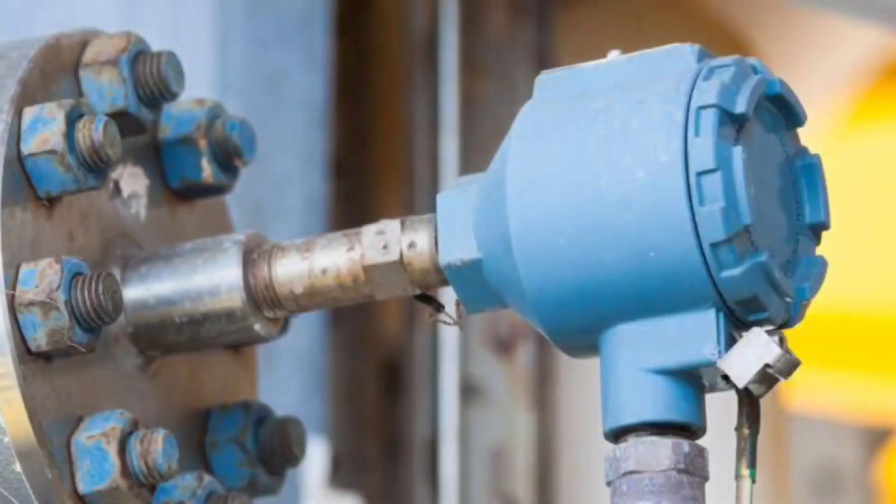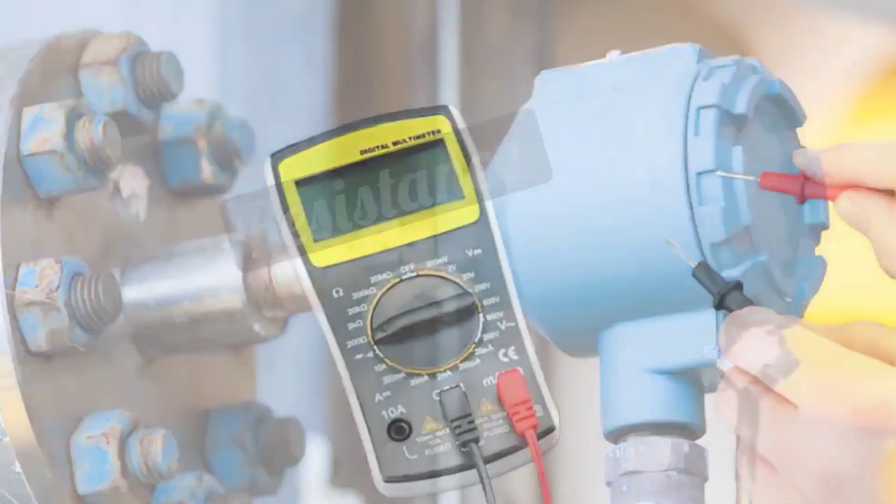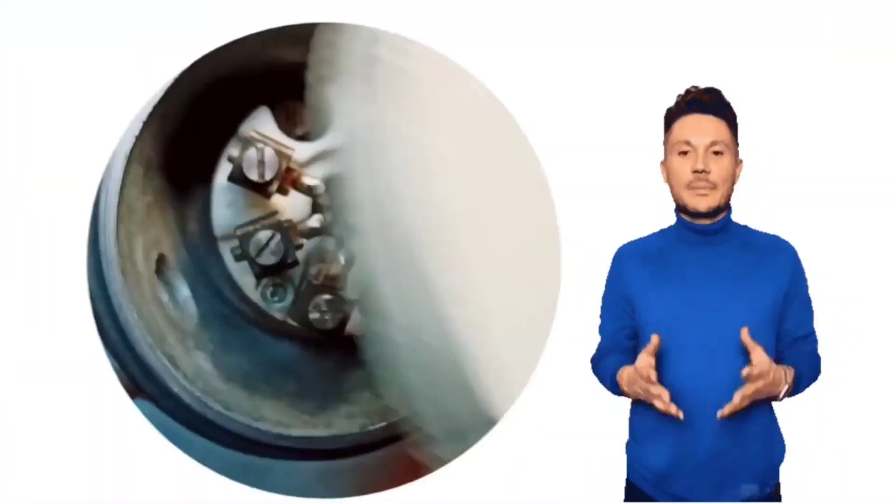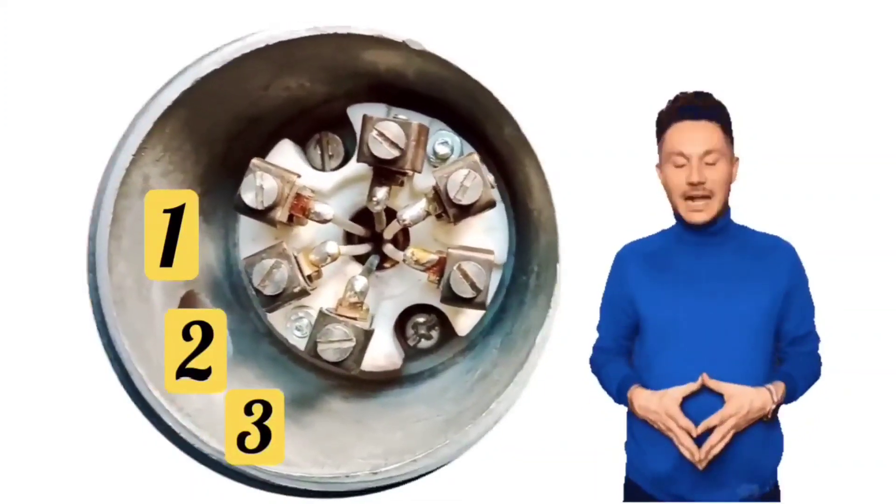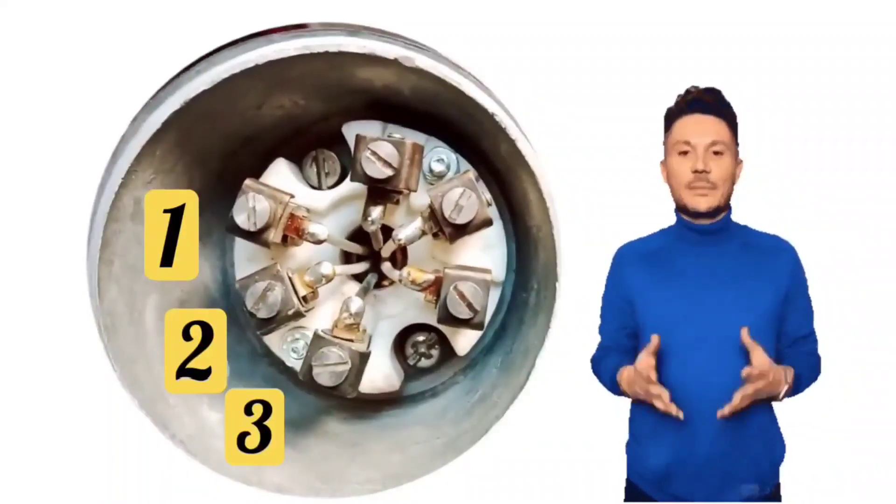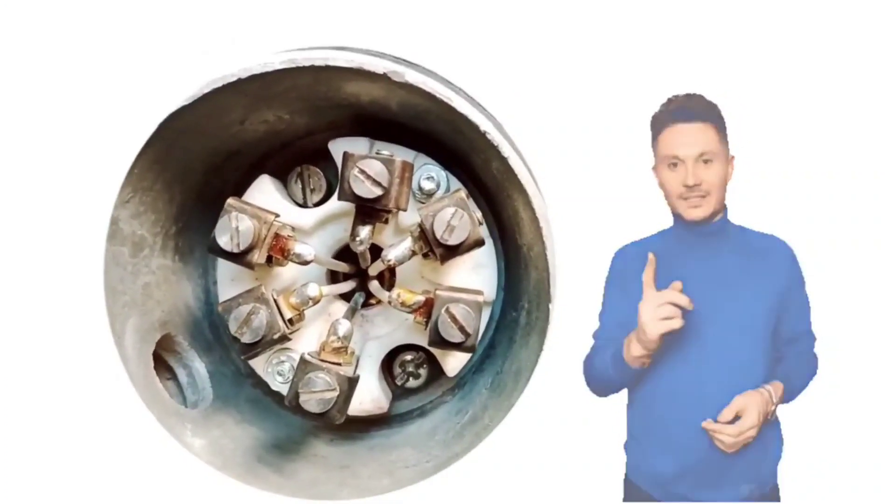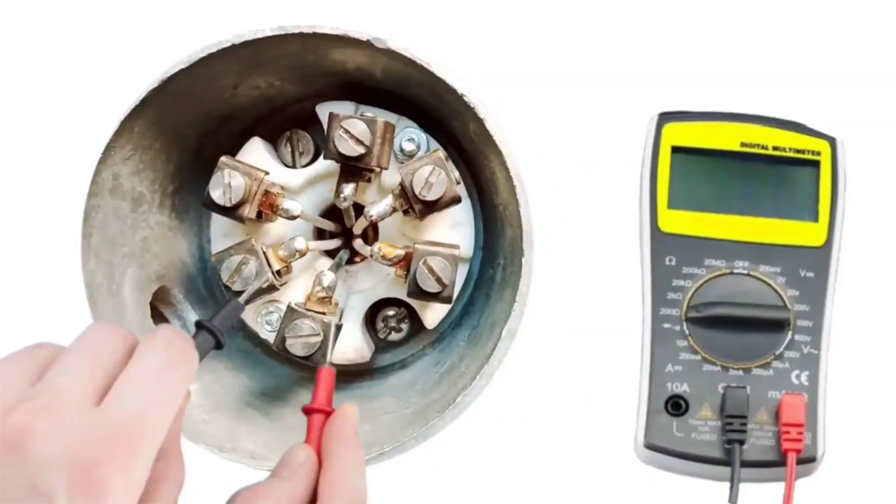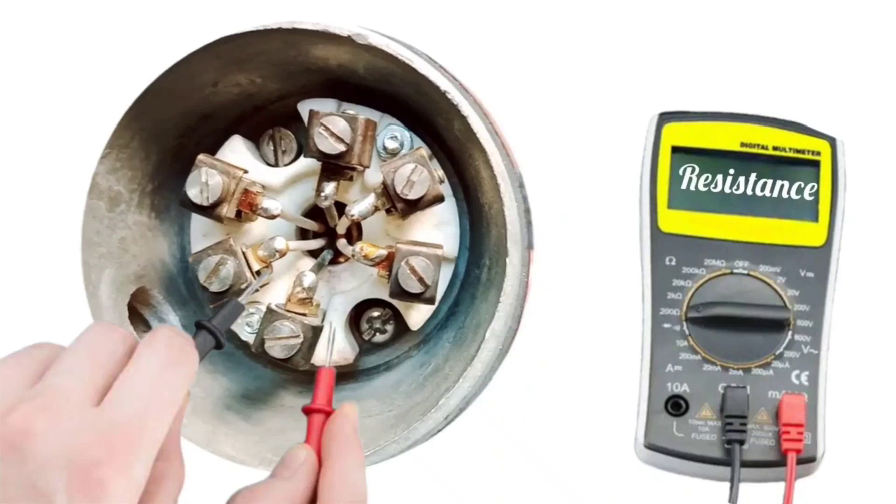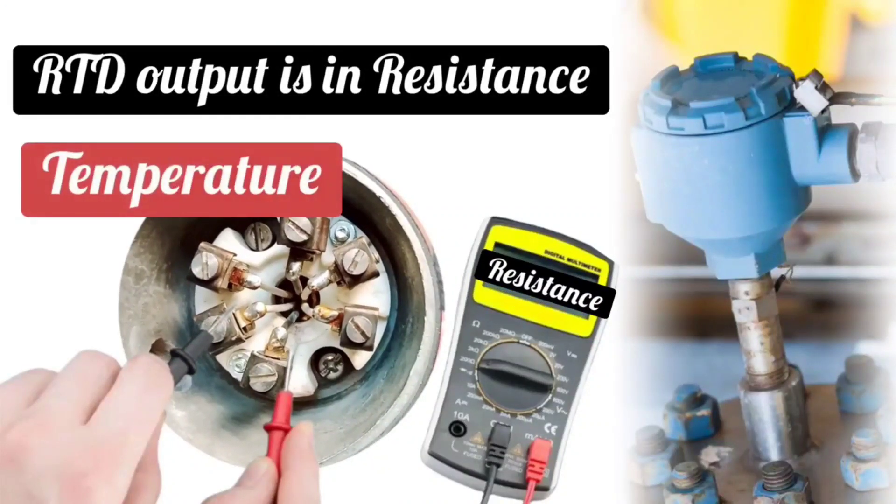When the RTD is checked by using a multimeter, resistance is measured. When you open RTD, you will see three wires. Two wires are of same colors, and one wire is of different color. Suppose two white color wires and one black color wire is there. One probe of multimeter is put at white color wire, and another one is put at black color wire. And we will check the resistance. Meaning, RTD's output is resistance, and from this resistance, temperature is calculated.